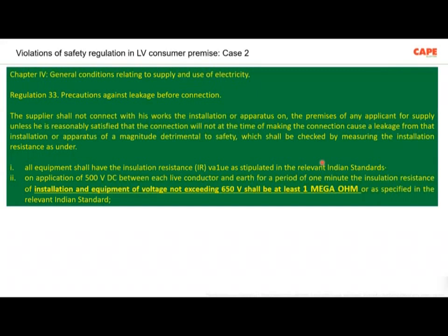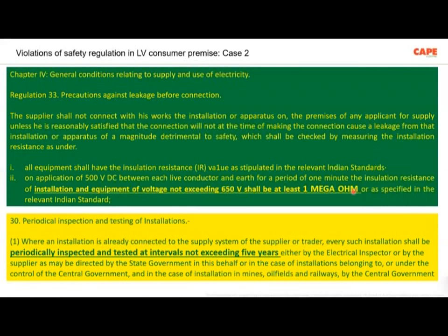case 2, regulation 33. Regulation 33 of the Central Electricity Authority Safety Regulations says, you can read the underlined part, installation and equipment of voltage not exceeding 650 volts shall have insulation resistance of at least 1 mega ohm. What is it? This is the minimum insulation resistance required in an electrical installation. 1 mega ohm between phase conductors to earth, between neutral conductor to earth. You have to disconnect the neutral and earth link, and you are supposed to measure the insulation resistance, and within your installation 1 mega ohm is the minimum insulation resistance required. I am explaining this because at the last part of the presentation I will show you a product which is sold in the market which actually violates this requirement.